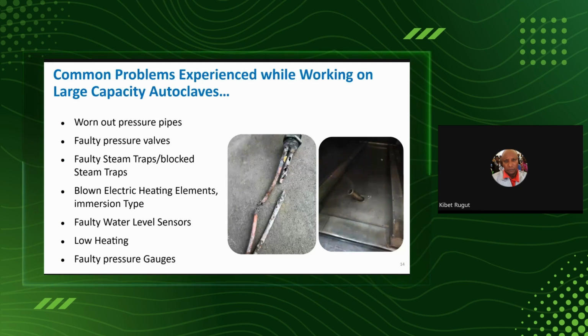Now, if the water level sensors are not working well, you will have too much water in the boiler, and it takes longer to attain the steam level, with slow heating. And then again, if the pressure gauges are wrong, you could be waiting for the pressure to be attained, but because the gauge is faulty, you are waiting longer than you should. So it's good to check every functionality of those areas that you should look out for all the time.